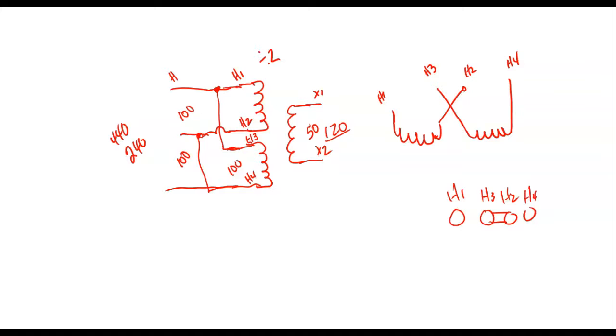A lot of people want to know why they cross them like that, why the screws are labeled H1, H3, H2, H4. They say, well, why do you need H1, H2, H3, H4? Because it gives us the ability to set it up for high voltage or low voltage with these little metal jumpers that come with it.